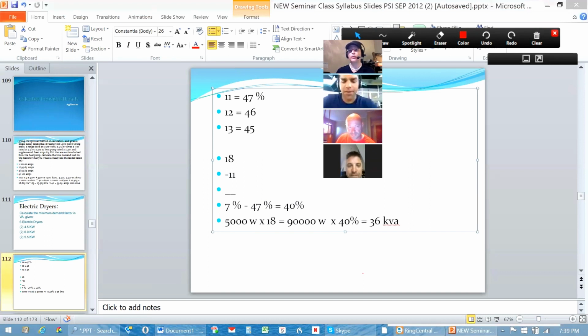But anyway, if this was a commercial question, I'm taking this 90,000 VA. I'm not doing any derating, but I'm not going to increase it for continuous duty either, because the nature of a dryer motor is that at some point, 60, 70 minutes or whatever it's going to be, it's going to stop for somebody to pull out that load and put in another load. The 3 hours is our mark where we start considering continuous duty factors, so dryers by their own nature would not be considered continuous duty. So if it's a commercial question and they gave me nameplates, I'd just take the full value at 100% and be done with it.